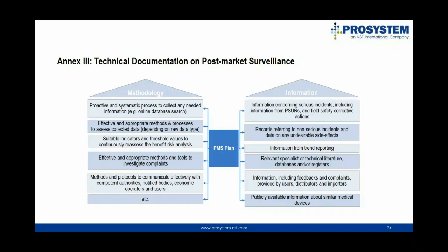Determining appropriate indicators and threshold values should be based on your current post-market experience with the device. That is, of course, if your devices have already been placed on the market under the MDD and you have experience data. If you do not have any market experience with your device, you should use the market experience data of similar devices, which may, for example, come from competent authorities' reporting databases. And after the completion of the PMS period, if you find that these estimates have been too high or too low, you will obviously have to update the plan as required by Article 83. This principle applies to all parts, not only of the PMS plan, but also of the PMCF plan that is required in Annex 14.